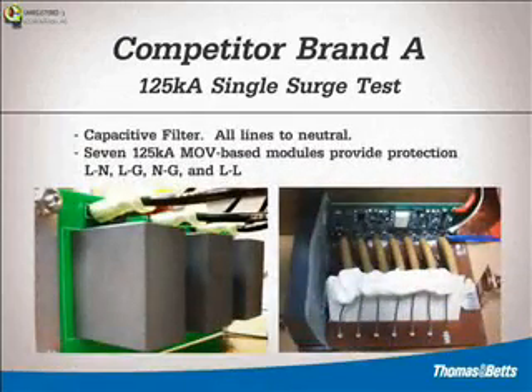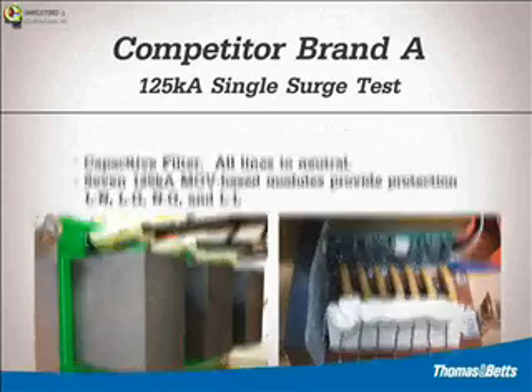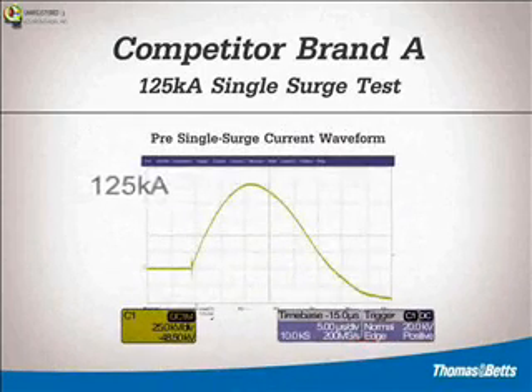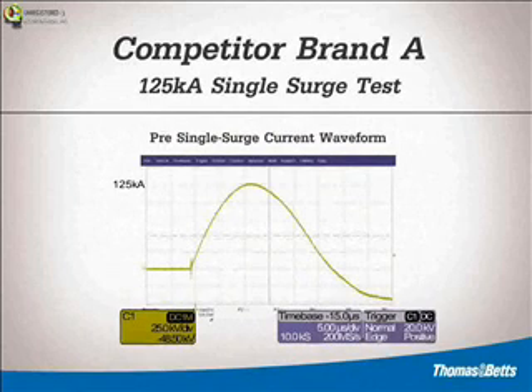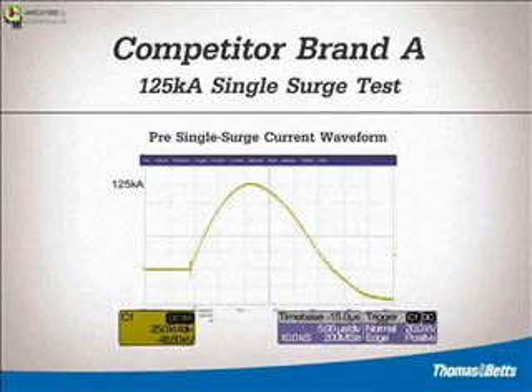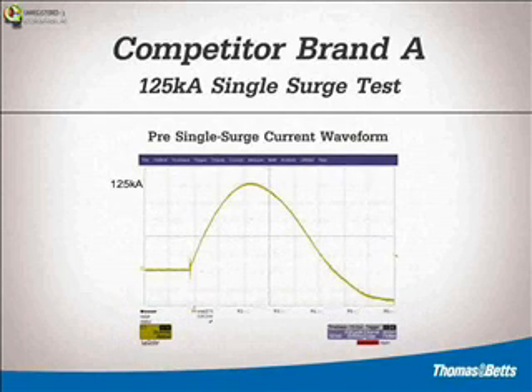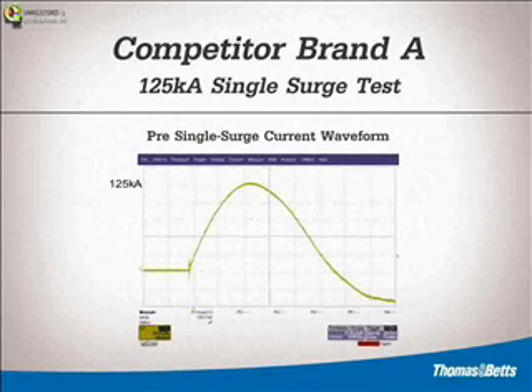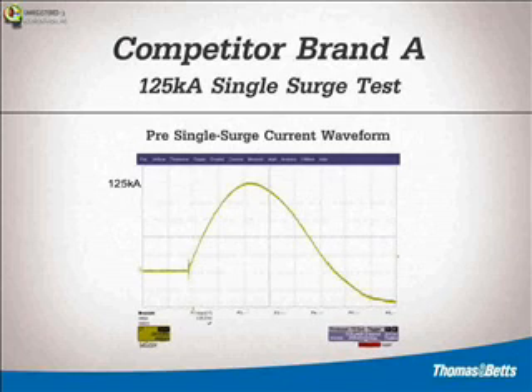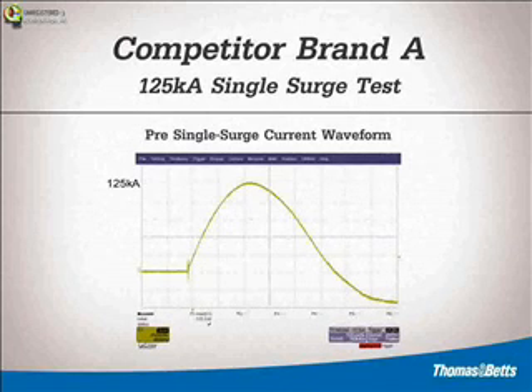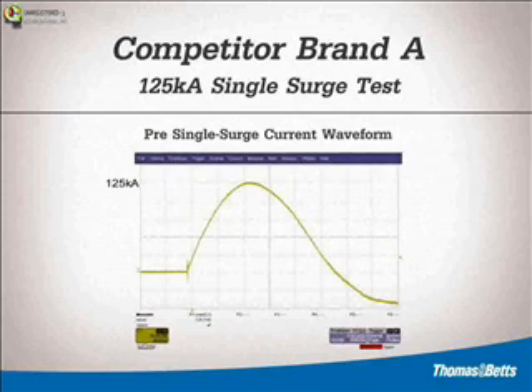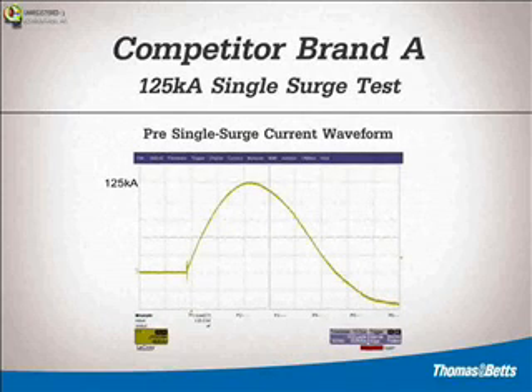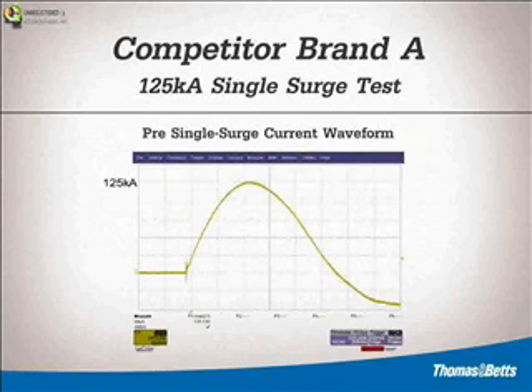Here is a glimpse at the inside construction of the model being evaluated. The inside of the unit revealed 7 modules, 1 per mode of protection, each claiming 125,000 amps of surge protection. When testing for single surge, it is first appropriate to document a calibration shot. The calibration shot helps determine what voltage level is required to achieve the desired surge rating. Once the desired surge rating has been achieved, the unit being tested is added to the circuit. The same voltage is used for charging the capacitors to ensure the desired surge current is applied to the unit. As can be seen from the current waveform, the calibration surge value was 125,000 amps.